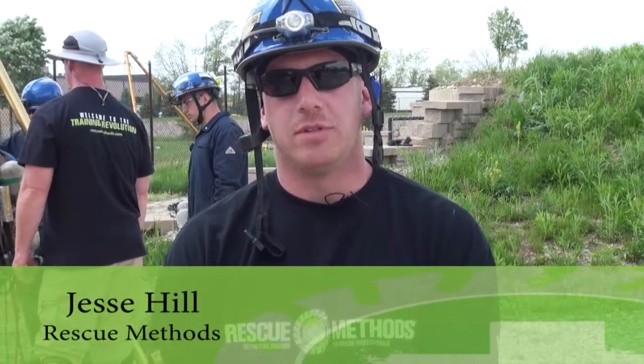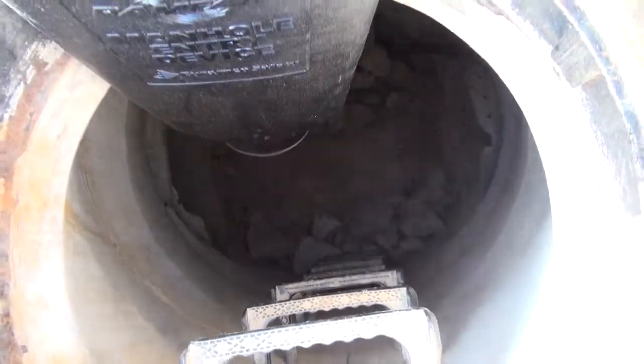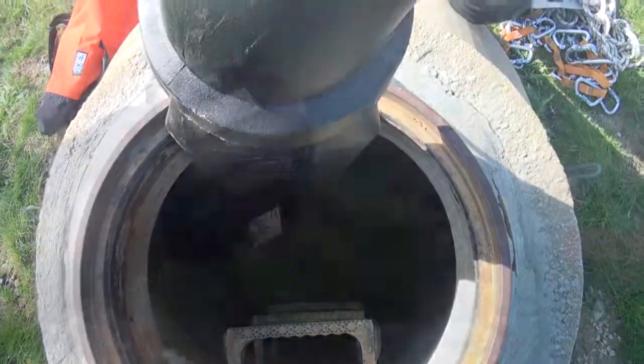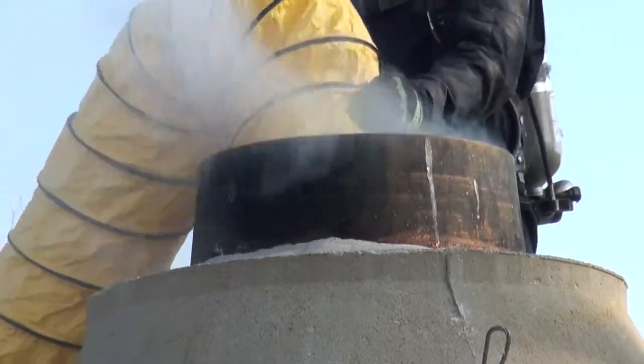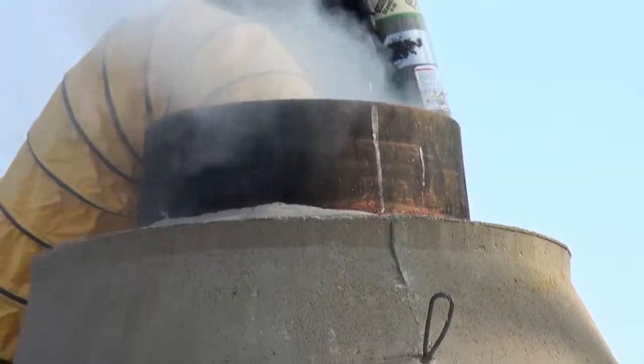All right, so when we're talking about ventilating our confined space environments and we're dealing with a constricted opening where we only have enough room to get one piece of ductwork in, we want to make sure that that ductwork is going to an exhaust fan and that we're trying to extract the contaminants out. What can happen is by using positive pressure ventilation there instead of negative pressure, we're going to create all of our exhaust coming out around that ductwork, making the area around our opening relatively unsafe to inhabit. We're going to have uncontrolled release of that product coming out.